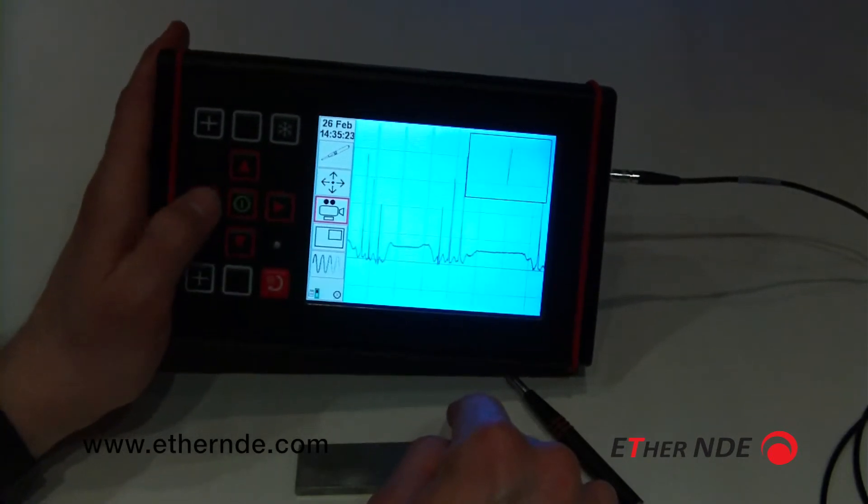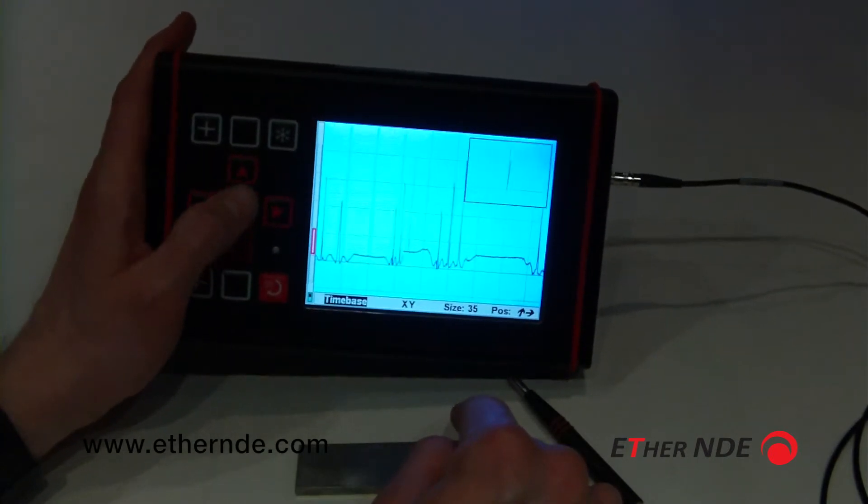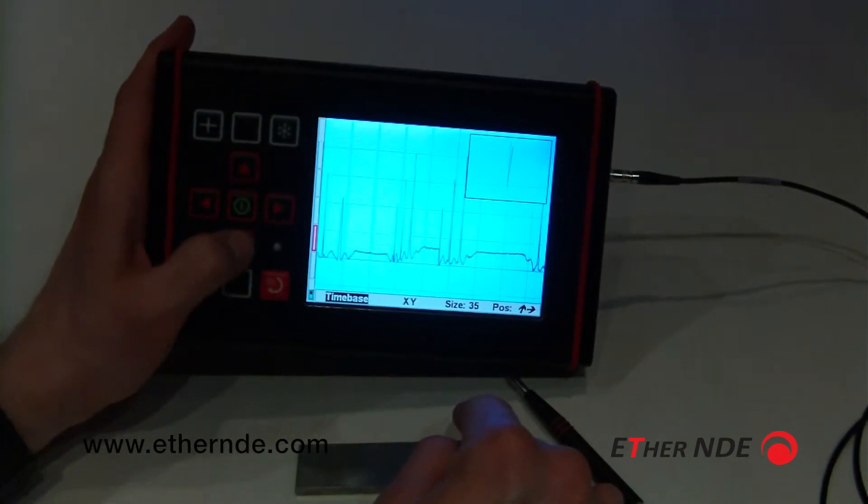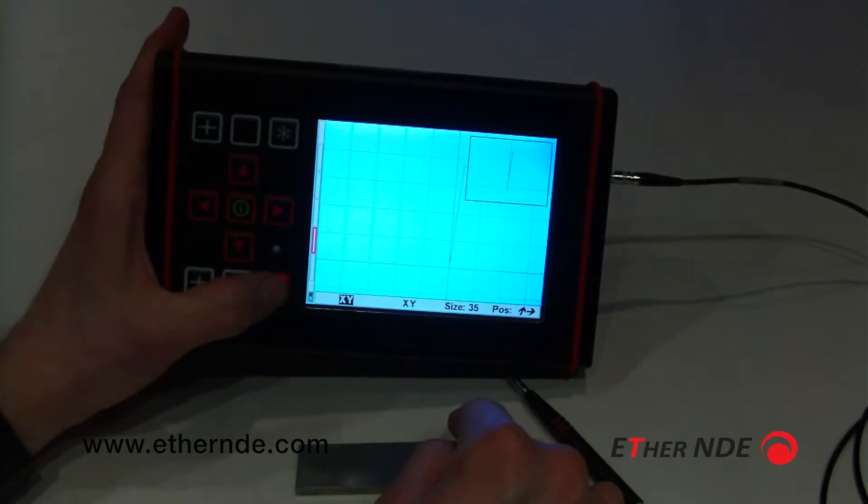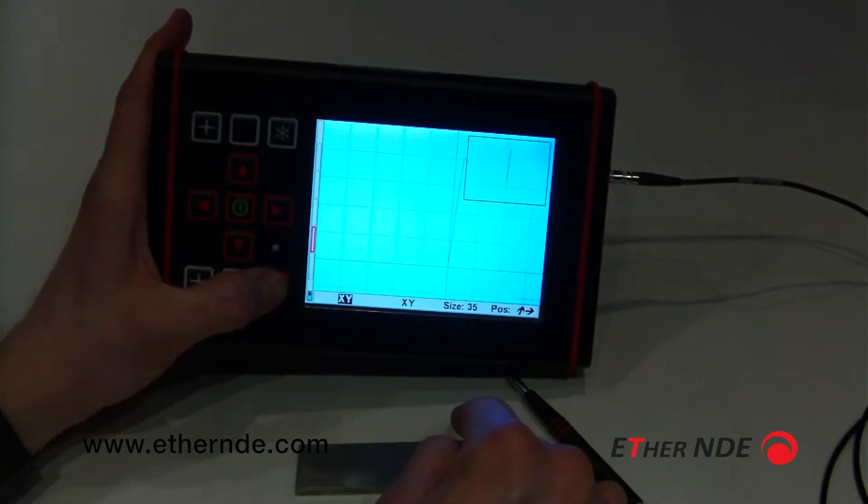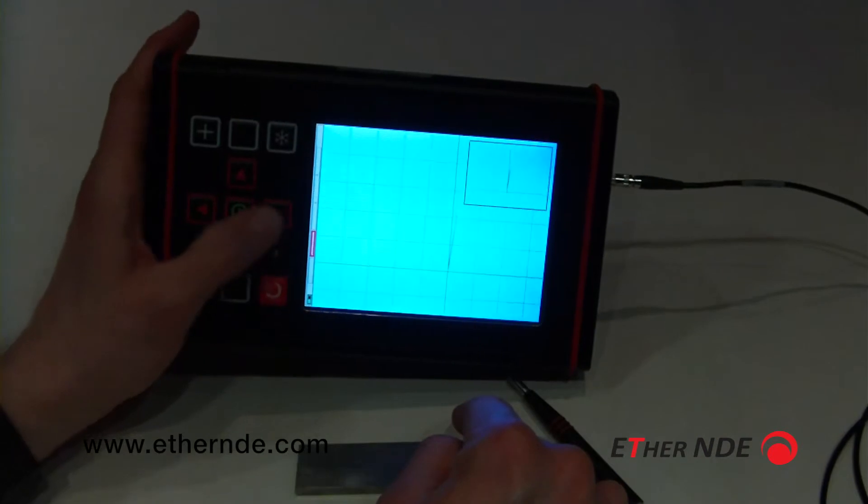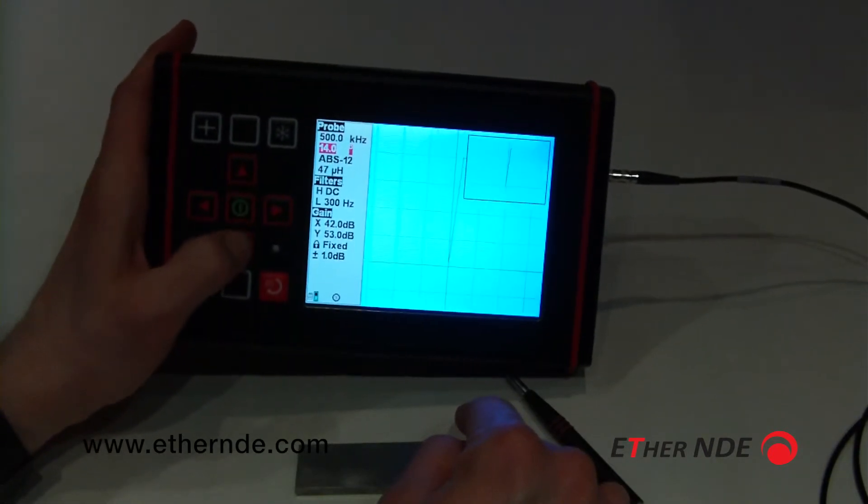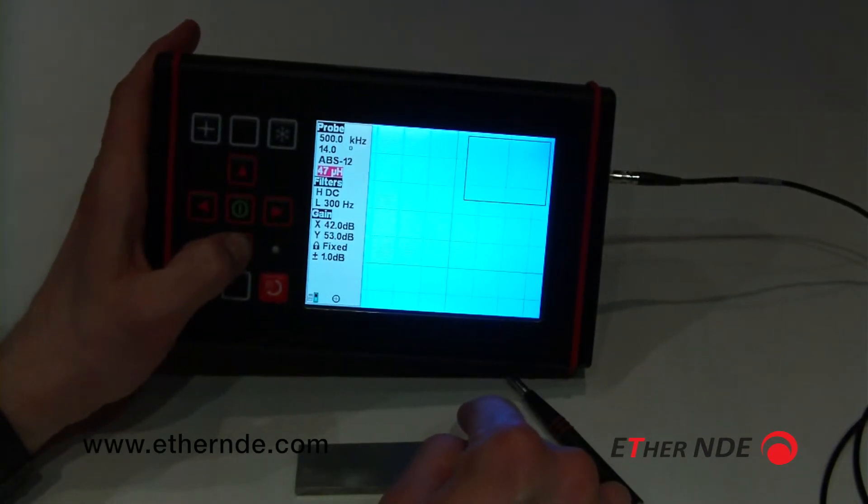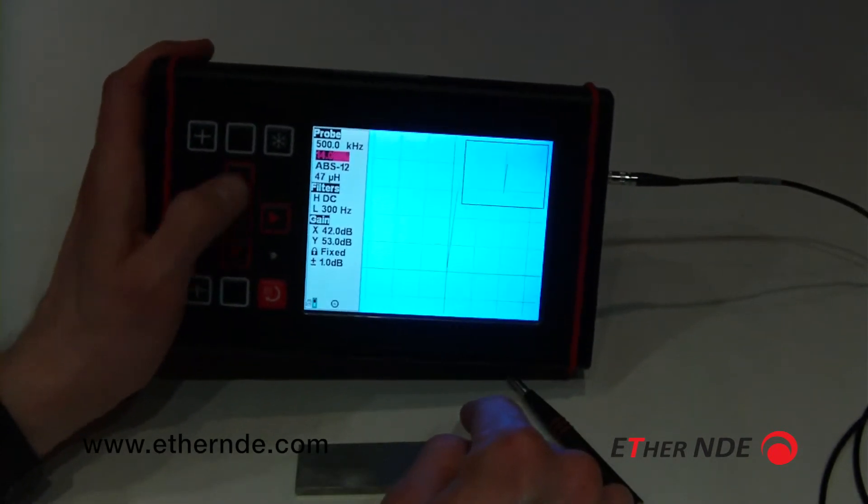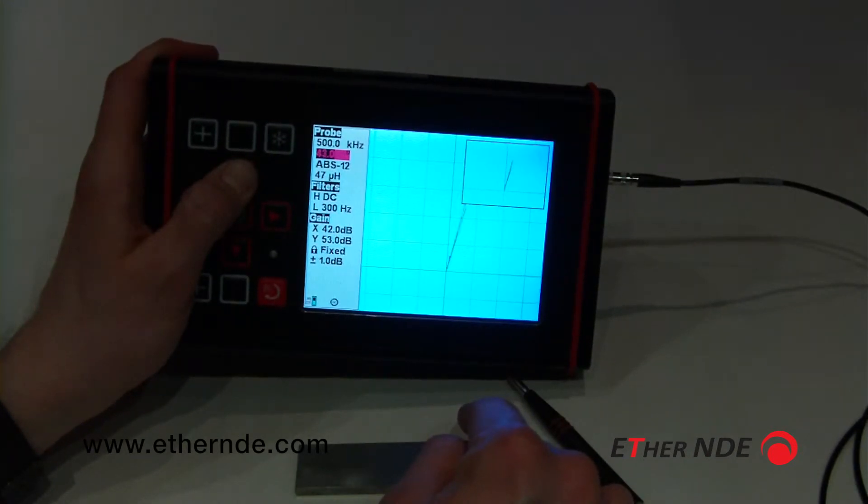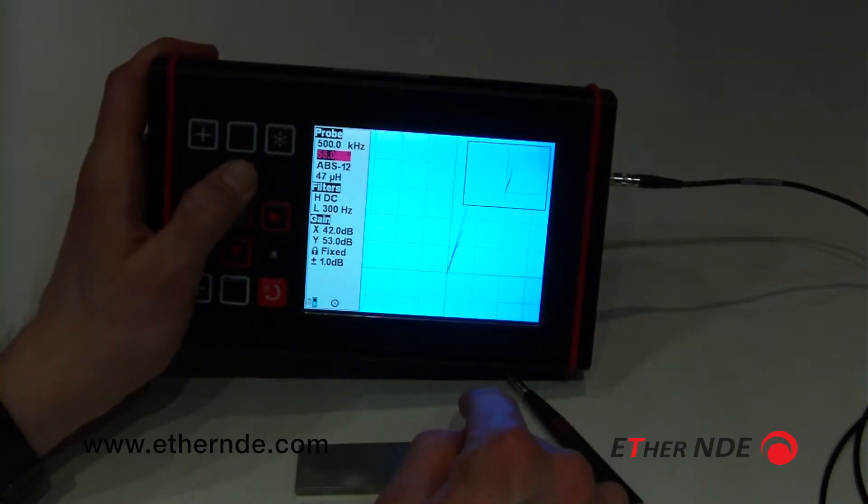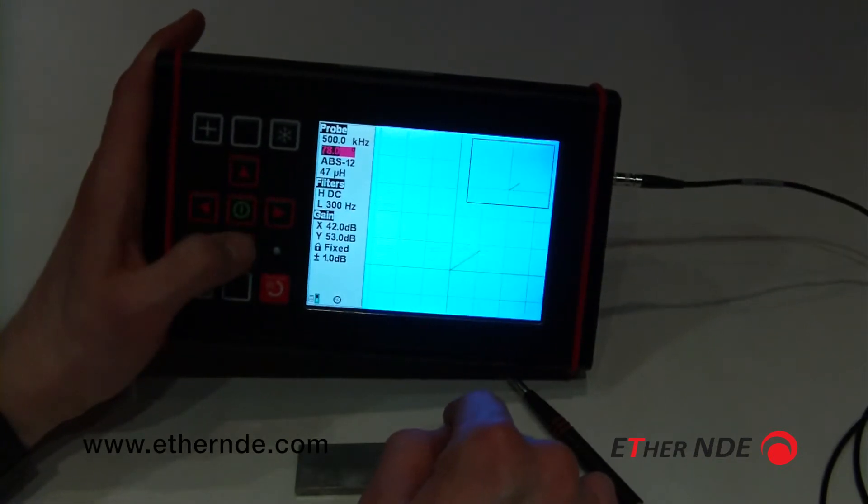Now I can close that. I can still go and edit any of the values. Let's put this back onto the phase plane display. I can change the phase of the data. As you see, the angle the defect is making is now changing as I rotate.